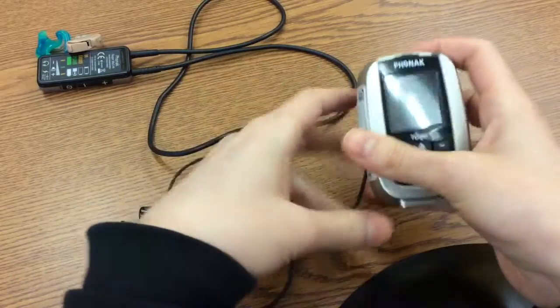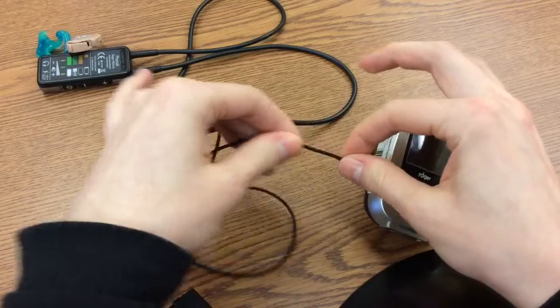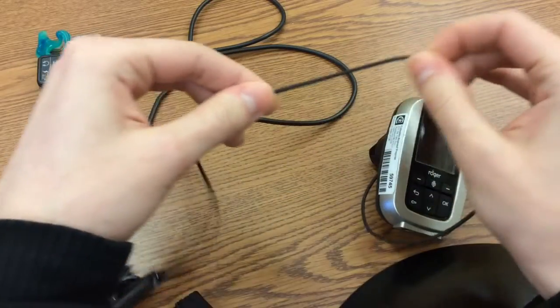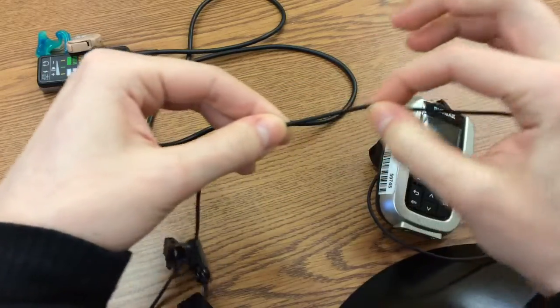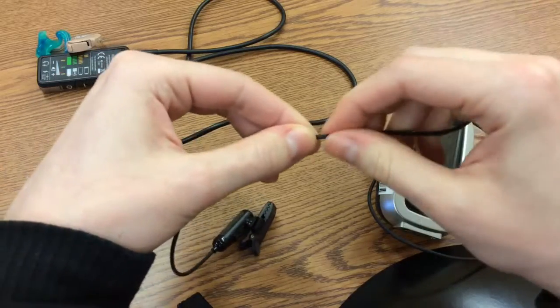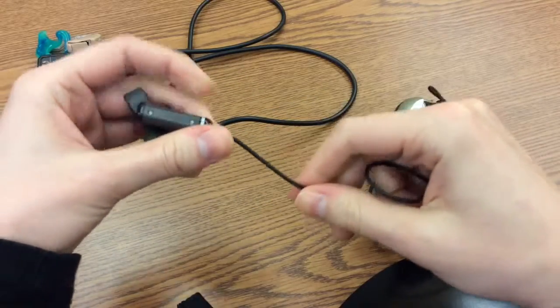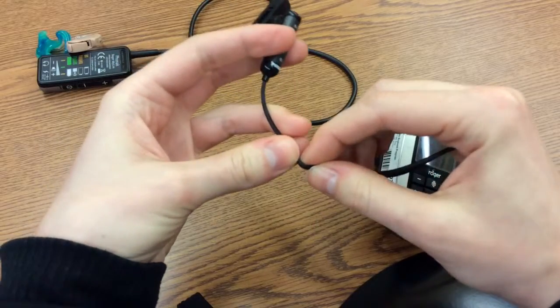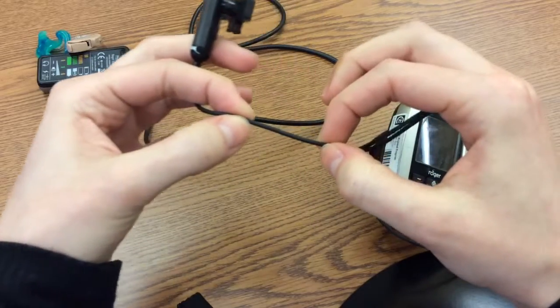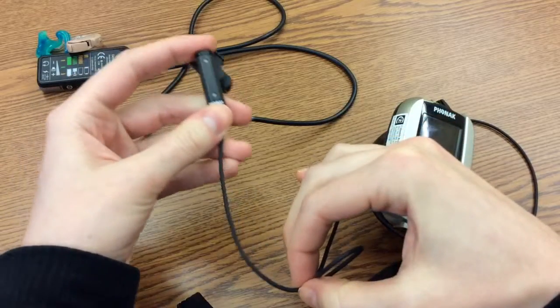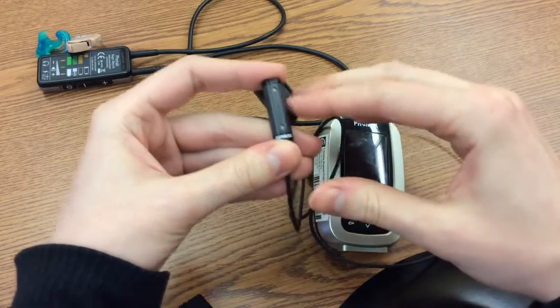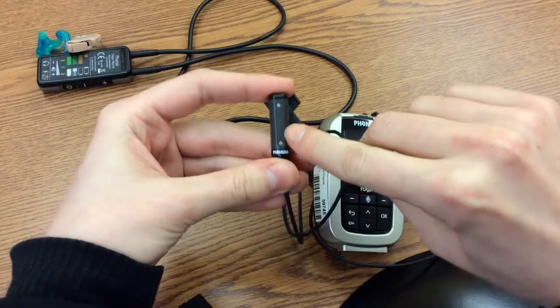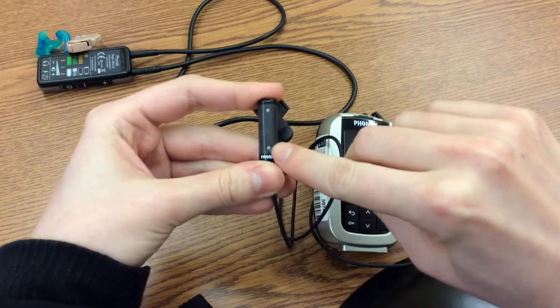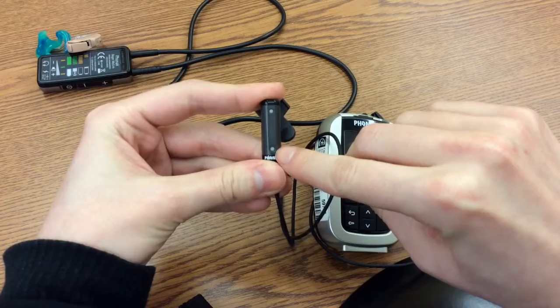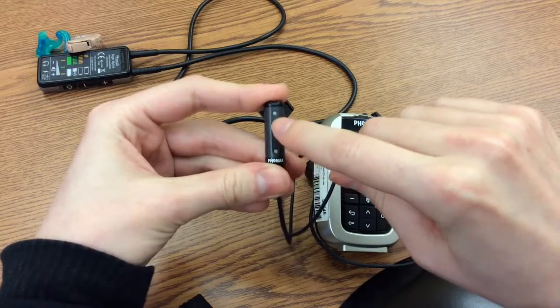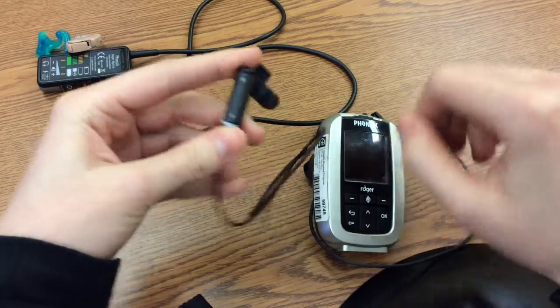When inspecting the body of the Inspiro, it's important to look at this wire attached to the microphone, because it's highly susceptible to little breaks. Since this microphone wire also works as an antenna, any kinks, bends, or tears will cause the transmission to be intermittent. It's also important to check that the two microphones are free from debris, since they're out in the open. Sometimes a little dirt gets caught in the microphones and that can affect the sound.